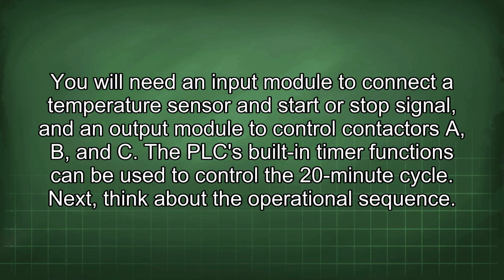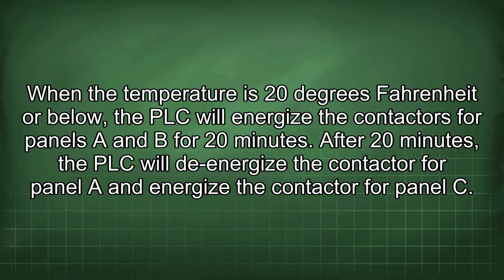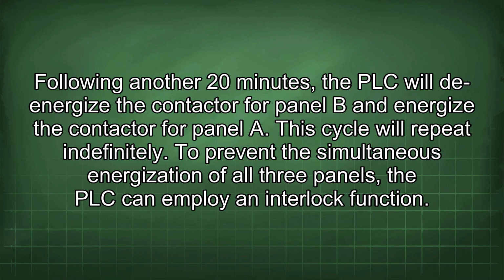Next, think about the operational sequence. When the temperature is 20 degrees Fahrenheit or below, the PLC will energize the contactors for panels A and B for 20 minutes. After 20 minutes, the PLC will de-energize the contactor for panel A and energize the contactor for panel C. Following another 20 minutes, the PLC will de-energize the contactor for panel B and energize the contactor for panel A. This cycle will repeat indefinitely.